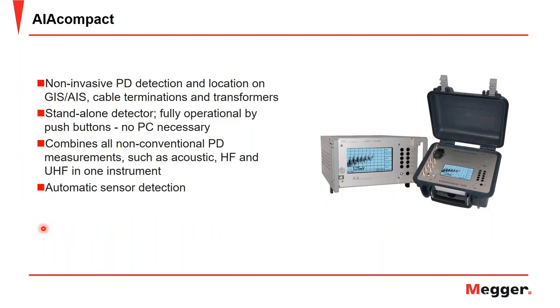And finally, we have here the AIA Compact, which is a non-invasive PD detection and location for GIS and AIS, as well as cable terminations and transformers. It is a standalone detector that's fully operational by the push buttons you see here. No PC is necessary, and it combines all of the non-conventional PD measurements such as acoustic, high frequency, and ultra-high frequency, so those electromagnetic and acoustic measurements that we covered in the unconventional methods, in one instrument, and also boasts automatic sensor detection, so no matter the sensor that you plug in, the instrument will know and configure itself appropriately.